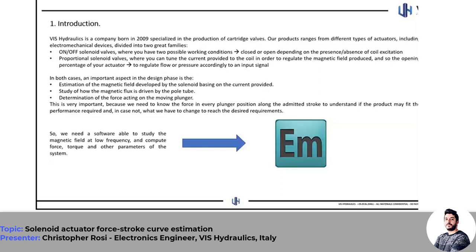In a proportional solenoid valve, you have different working points depending on the amount of current injected in the coil. An external controller tunes the current via PWM modulation according to an input signal from a controller or joystick, allowing you to tune the magnetic field and the force acting on the plunger, and regulate the opening or closing percentage of the actuator to control flow or pressure in a hydraulic circuit.